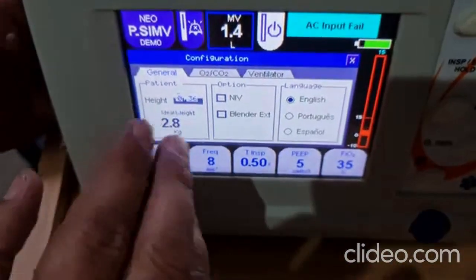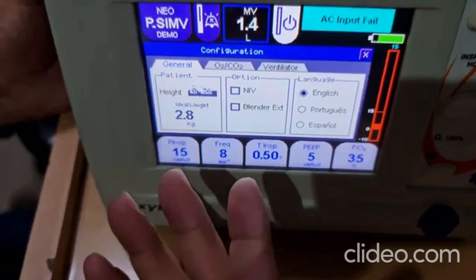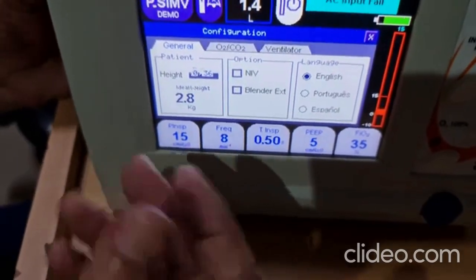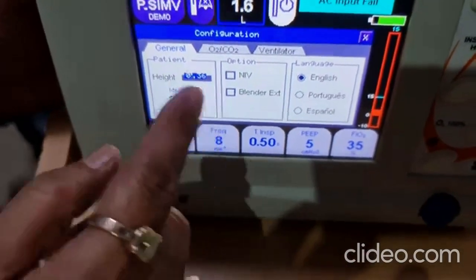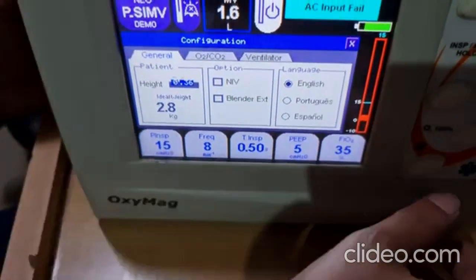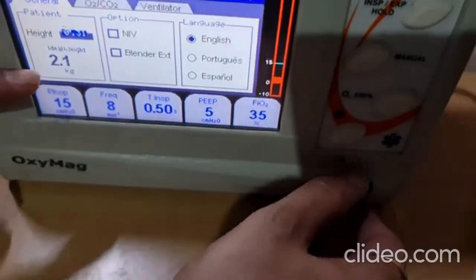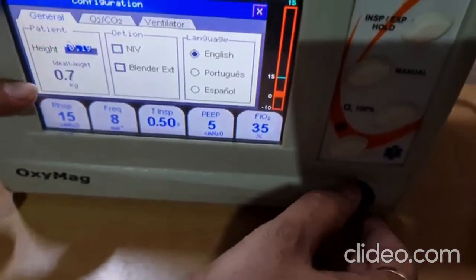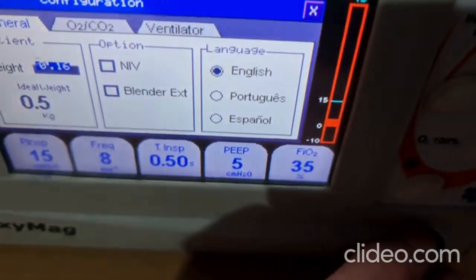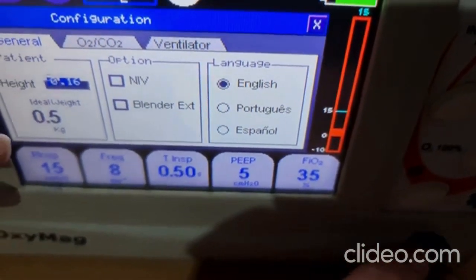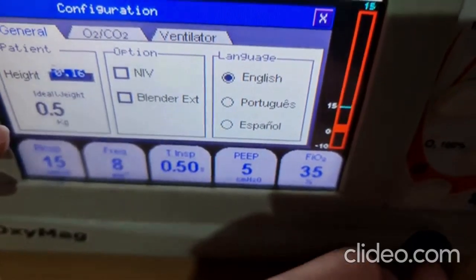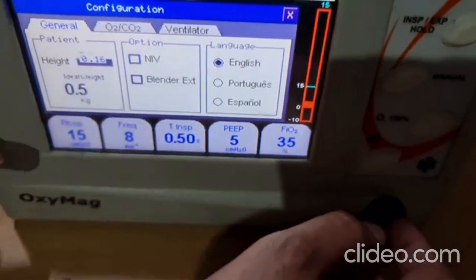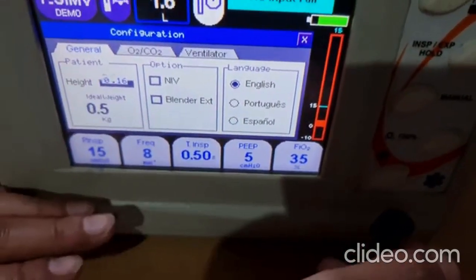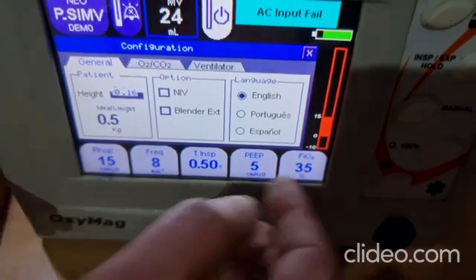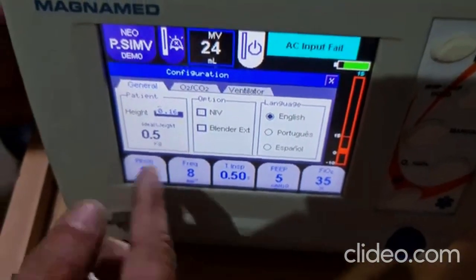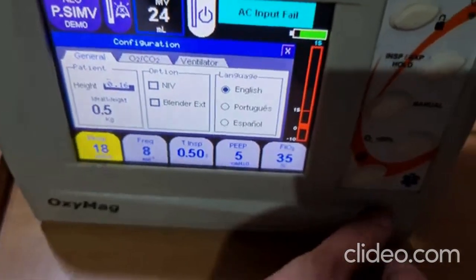Next is configuration. In configuration, you can adjust the parameters by putting the patient's weight. So see, we have selected the neonatal patient. Now we are adjusting the weight. So you can use it for the premature baby also. Say the weight is 0.5 kgs. From the 0.5 kgs, if you select weight, it will select automatically the other parameters according to the weight. If you want to tune it fine, you can increase or decrease parameter after that also.